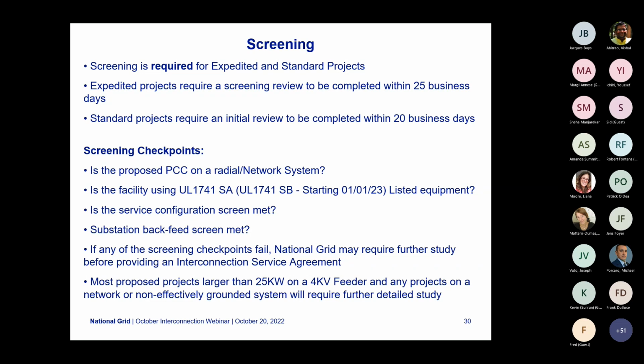Other reasons that projects under 250 kW could require further study are that they could be proposing to interconnect in a challenging area, in an area with an ongoing group study, and then those projects will need to progress down the standard path. Most 4 kV projects, any projects interconnecting onto a 4 kV feeder, typically require further study due to the limitations we have on those feeders. And then every project proposing to interconnect to a network or non-effectively grounded feeder will require further study. Next slide, please.